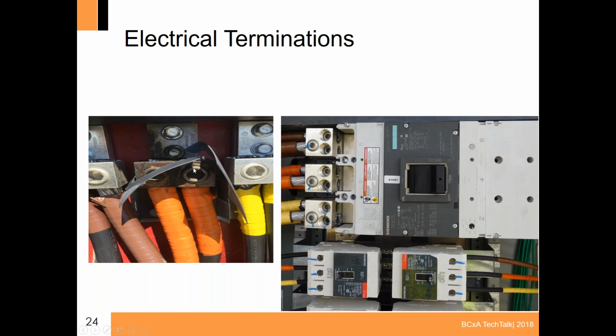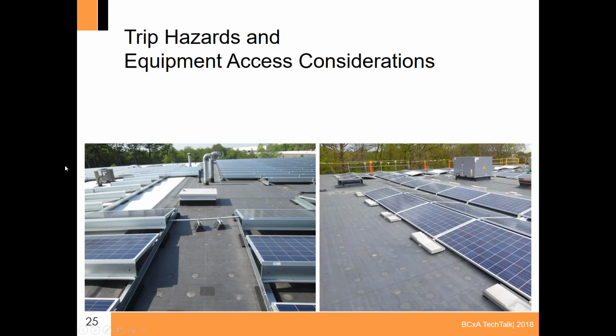We have our torque wrenches, torque screwdrivers, and good practice is something like this on the right-hand side, where we run around with a paint marker and we verify. That's basically an unofficial industry standard that we mark these terminals with the paint marker to indicate that they're properly torqued. So that's one of the other verifications we do during the installation. Make sure that people are using the torque wrenches, and make sure those wrenches are set to the proper setting as well.